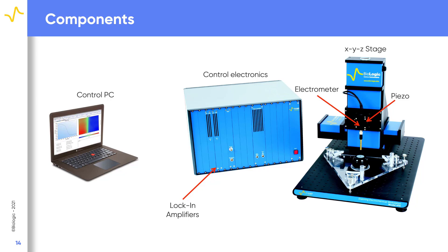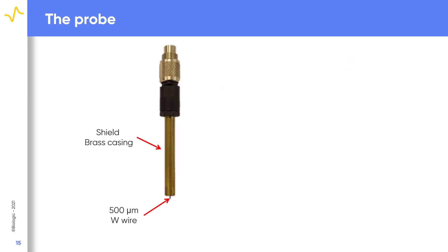The electrometer is required to measure the electrical potential of the system. The backing potential controller applies the potential required to null the charge between the probe and sample, done in real time using a PID control loop. Because the probe-to-sample distance affects the final signal measured and therefore sample tilt can affect the measurement, it is important that the sample can be mounted to remove tilt. On the M470 this is typically achieved using the tricell. Of particular importance in the SKP measurement is the probe, which affects the resolution and quality of the final measurement. Biologic's standard probe is a 500 micron tungsten wire within a brass shield, used to reduce parasitic noise in the measurement.